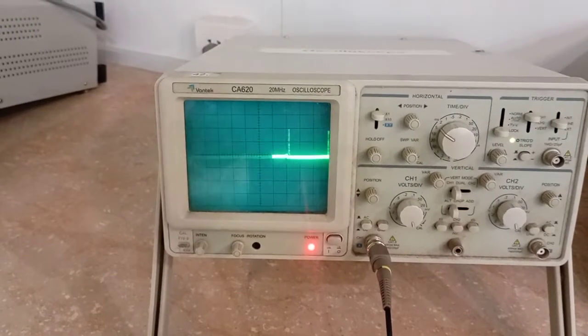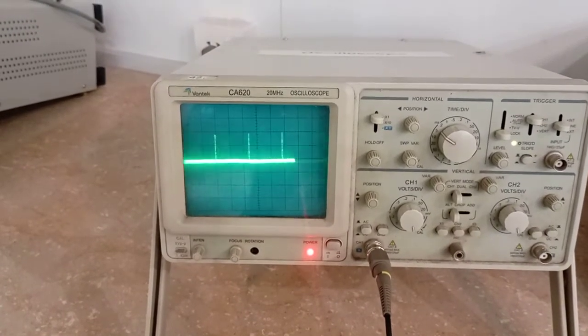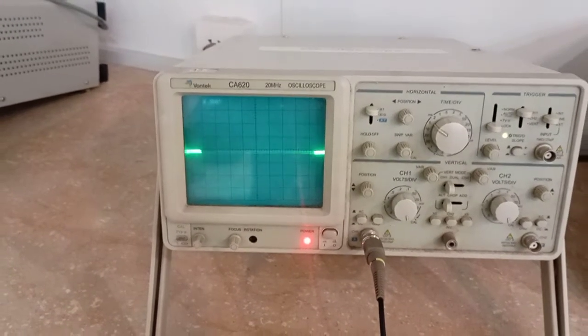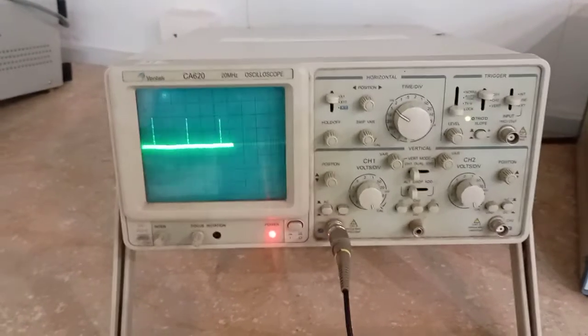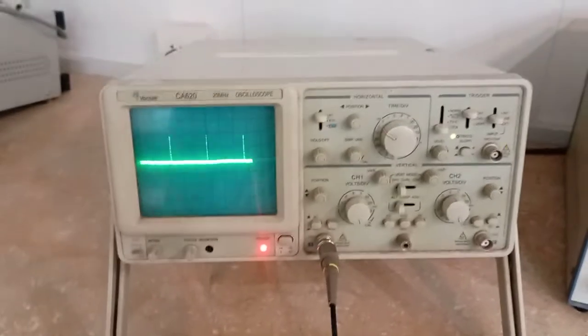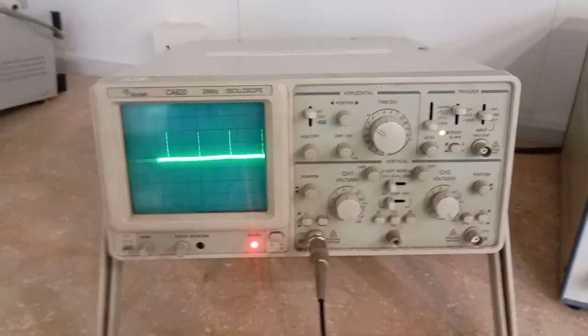difference on the oscilloscope. But if it is kept in the normal mode and there is no modulation of the frequency, then these lines will appear symmetrical, and similarly they will be there for the whole treatment time. So that's how you visualize the waveform of TENS on the oscilloscope.